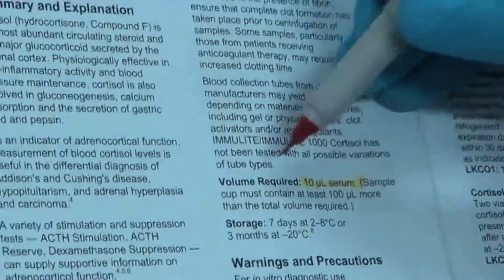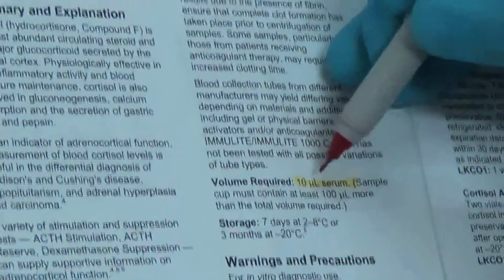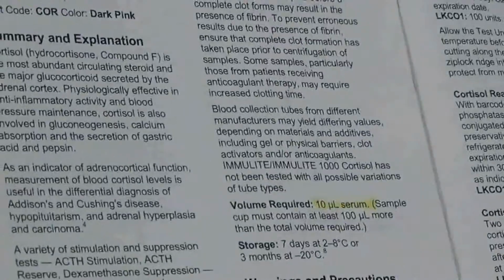And now it's asking me to actually load my reagents, which we've done, and the sample, which I now have to pipette. For cortisol, it is asking that we have at least 10 microliters of serum. Because there is a very precise level to which this probe has to descend, it has to be more than 10 microliters. It needs at least 10 microliters for a sample to run, but you have to load 150 microliters of serum so that it will not damage the probe.